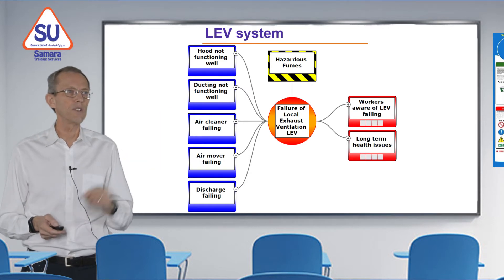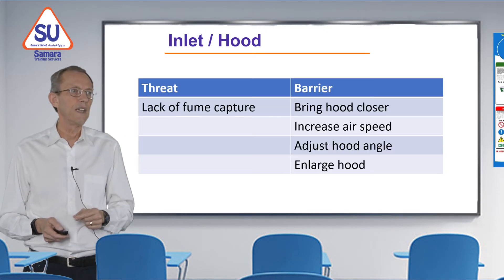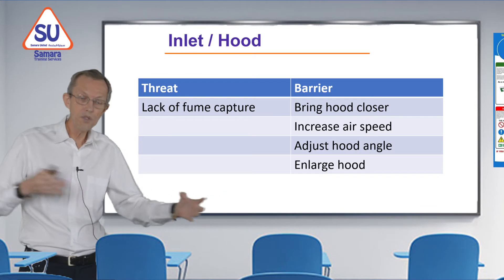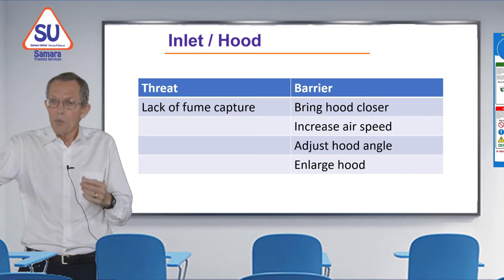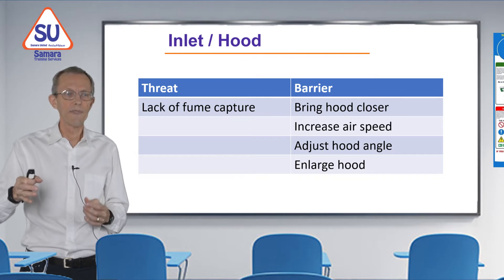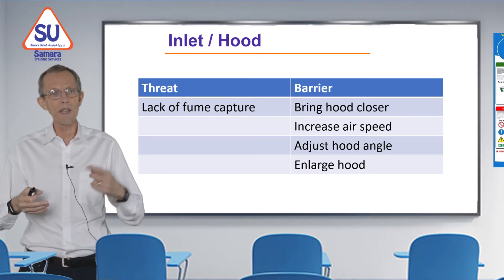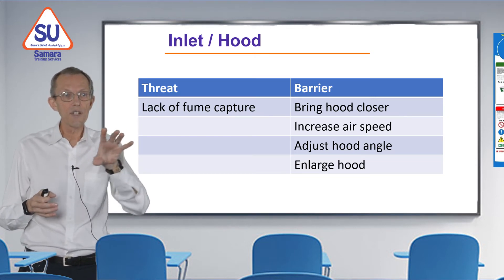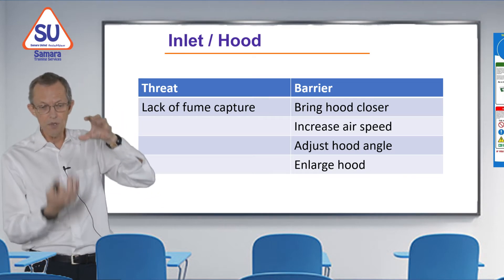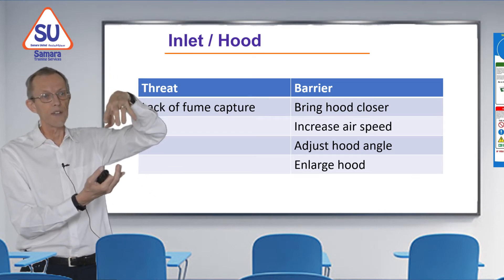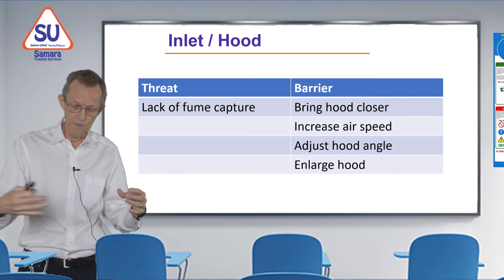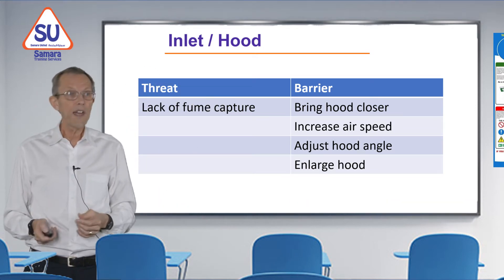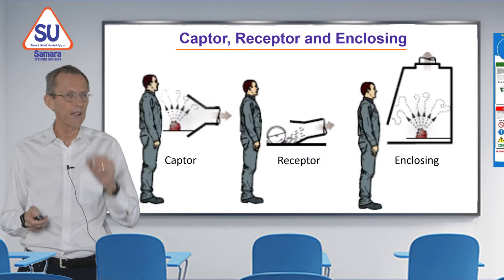Let's look at the first threat: the hood not functioning well. If we don't capture the fumes or dust properly, the fumes are available for people to breathe — we don't want that. So we could bring the hood closer. Another thing we could do is increase the air speed, sucking more air in. We could also adjust the angle of the hood so it better catches the fumes — if fumes are rising, we put the hood above; if they're produced sideways, we catch them that way. Or we could enlarge the hood. If we put that on the bow tie diagram, that will come up in a minute.